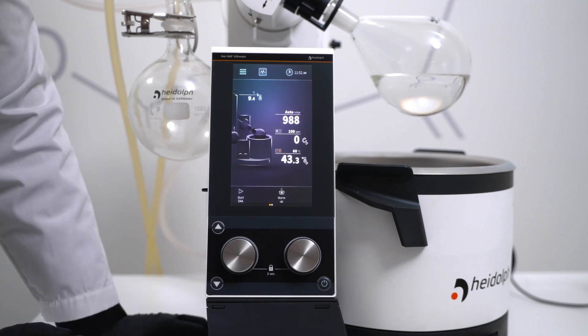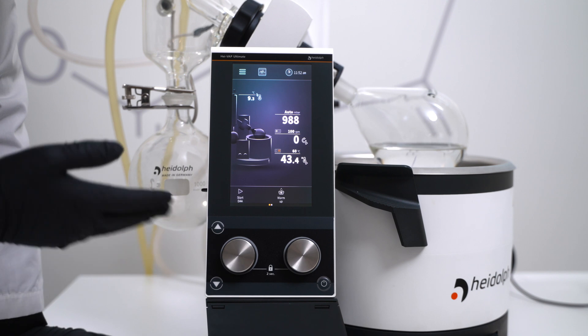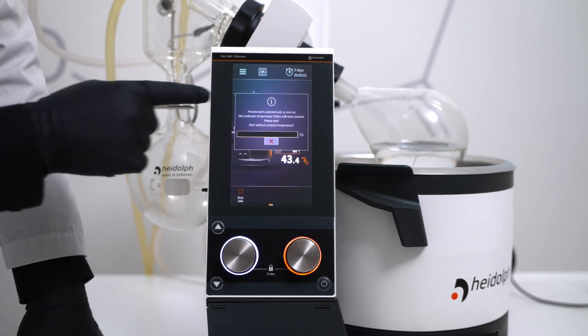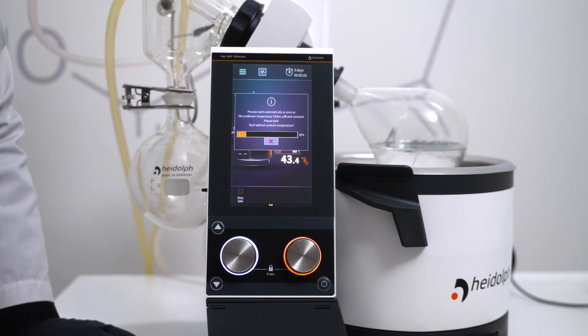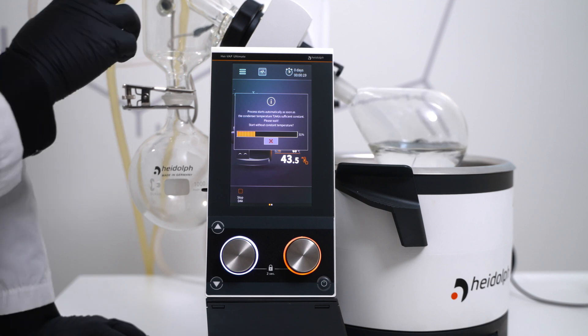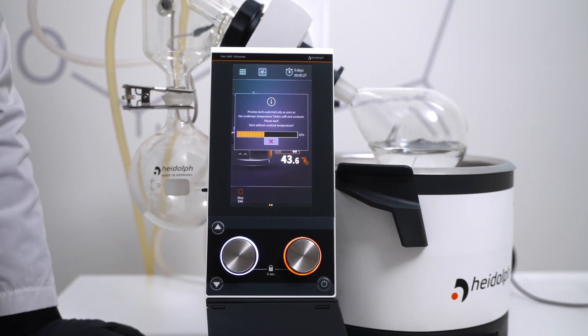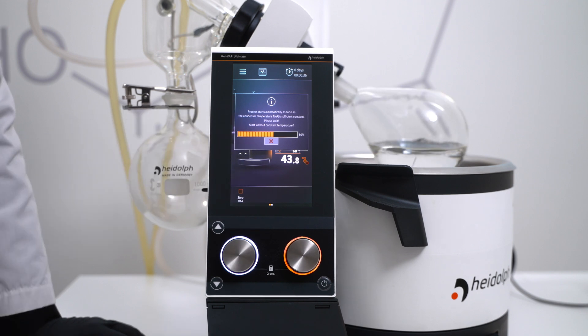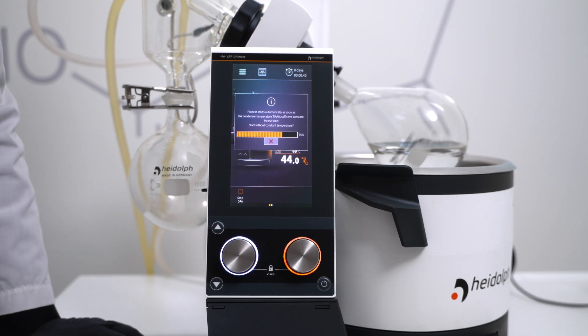Once all of those settings are completed, we can lower our evaporation flask into the bath. This can also be done automatically if you have a preset on your ultimate control or expert control. And we're going to hit the Start DAA button. This loading screen is going to pop up, and what that is doing is basically making sure that the temperature being read by the temperature probe is stable. It basically just makes sure that the temperature probe is not changing in temperature by more than about 0.1 degrees per 20 seconds. Once it is measured that everything is stable, it will begin pulling down the vacuum. But from here, you're already basically ready to walk away and allow your evaporation to occur.